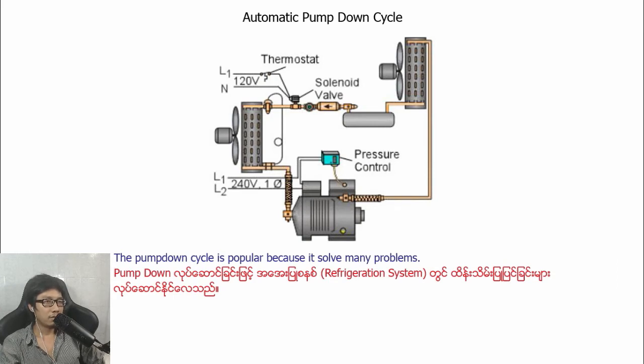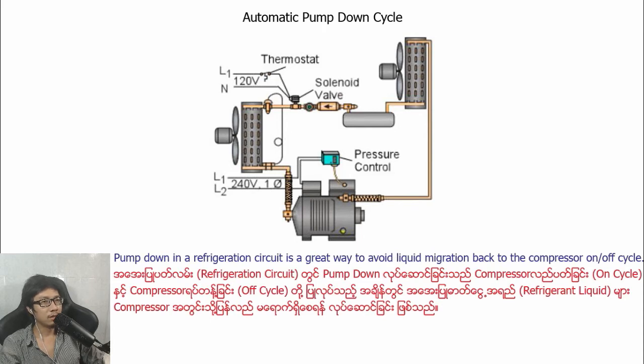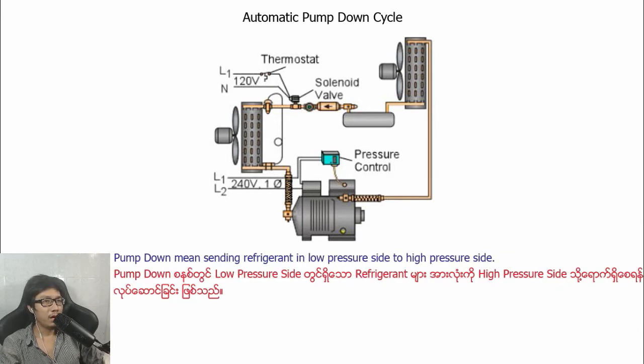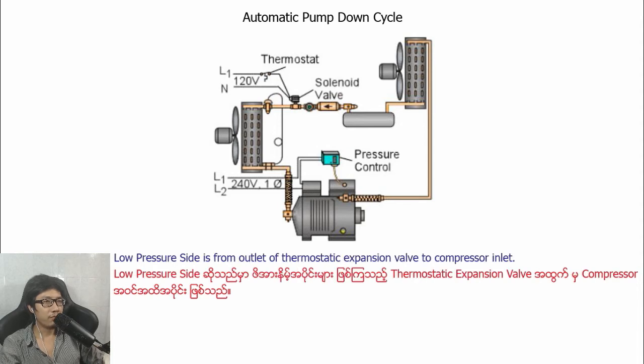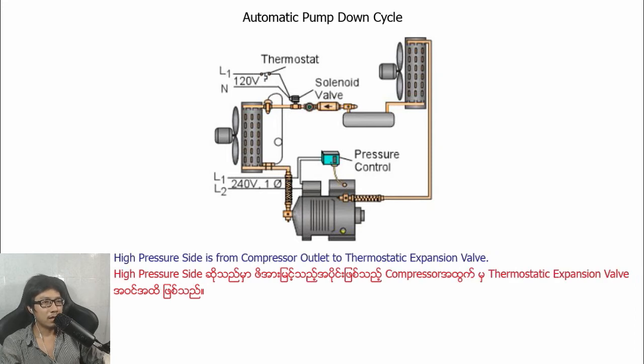The pump down cycle is popular because it solves many problems. Pump-down in a refrigeration circuit is a great way to avoid liquid migration back to the compressor on-off cycle. Pump-down means sending refrigerant in the low pressure side to the high pressure side. The low pressure side is from the outlet of the thermostatic expansion valve to the compressor inlet. The high pressure side is from the compressor outlet to the thermostatic expansion valve.